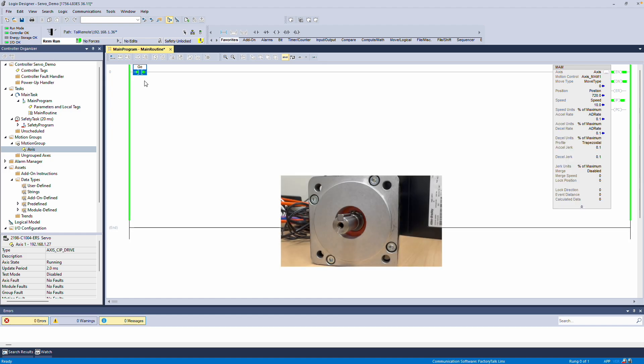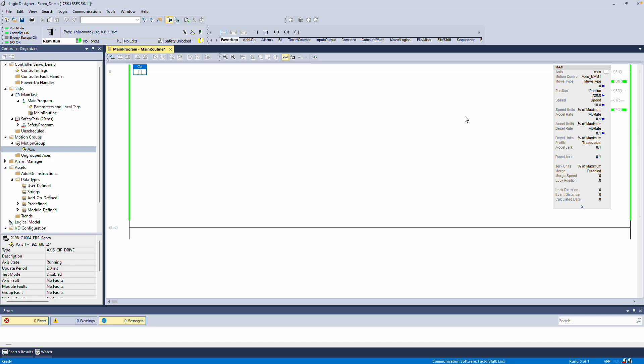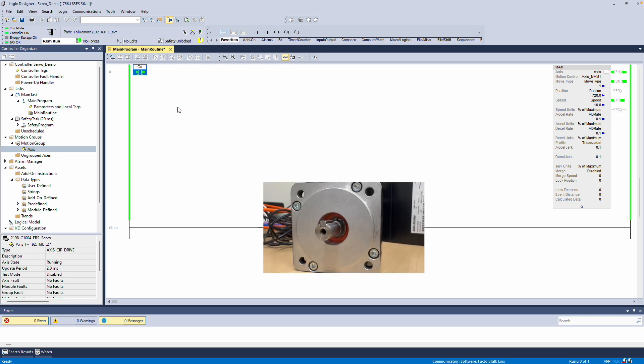When I toggle Go, the servo drive will move. If I change the Move Type to Incremental and toggle it again, the servo will rotate 720 degrees, or two full revolutions, each time. That's how you program logic for this setup.